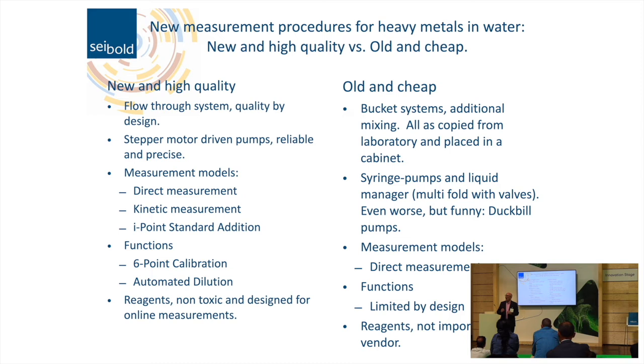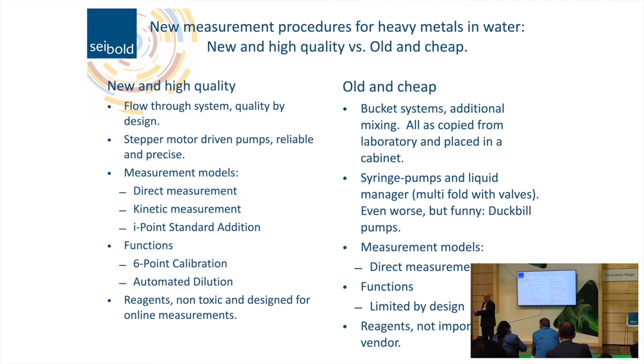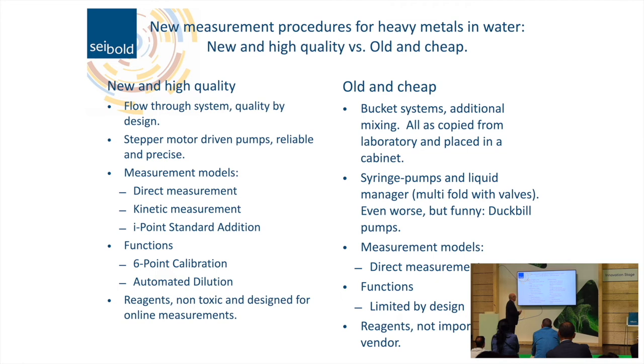Coming back to the flow-through system: it not only reduces instrument complexity and increases operational stability, but also provides additional functions by design. Bubble detection — if a bubble passes the photometer you see it like a black shadow, so you can detect missing solutions automatically. Mixing of solutions is done automatically without extra devices. We have automated dilution: if a value exceeds measurement limits, you can automatically re-measure with dilution without disruption. Competitors need additional separate devices for this.